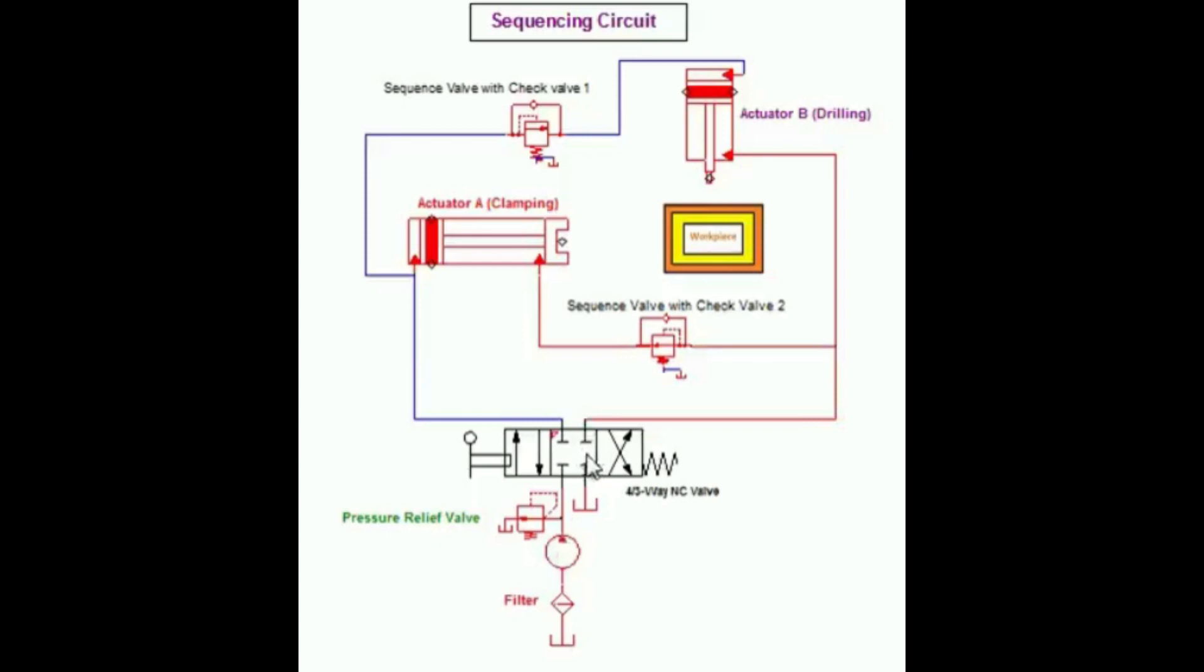of the circuit until the clamp cylinder has reached the end of stroke. When the clamp cylinder extends completely, the pressure rises and opens the sequence valve, thus allowing the drilling cylinder to extend.